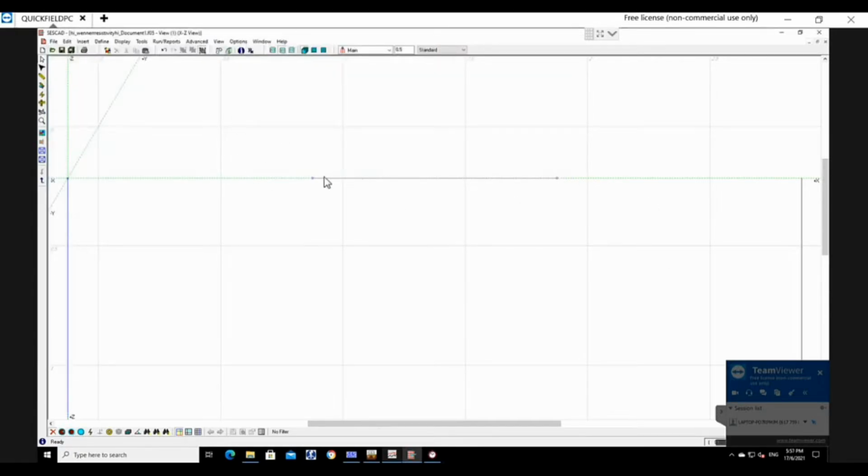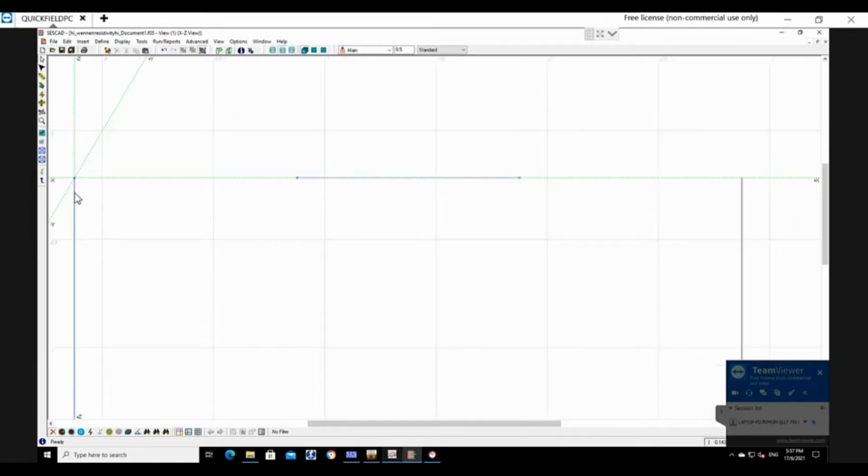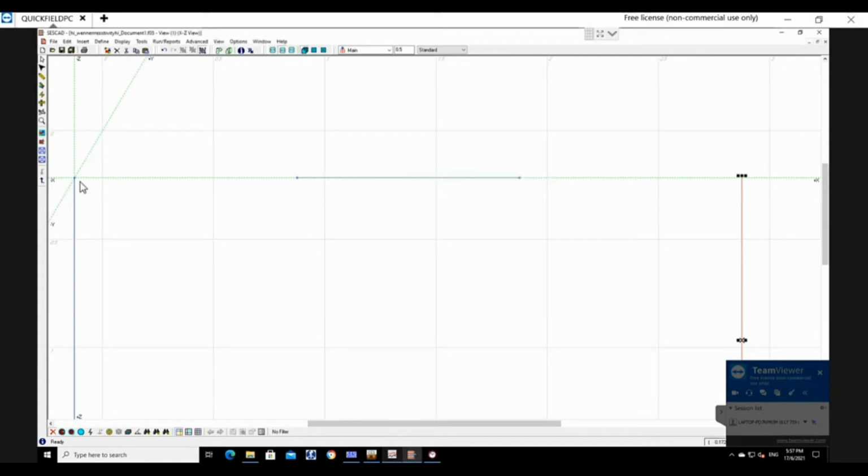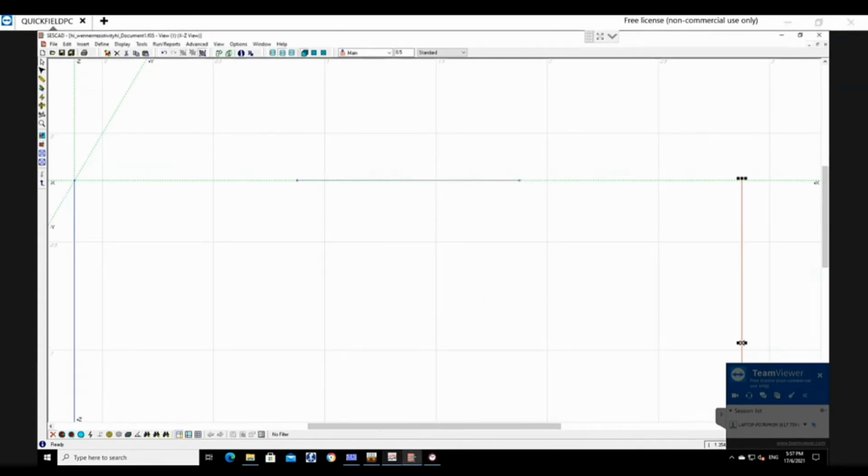For the second part, we need to change the current probe's length to 1.5 meter, and take the reading based on the data, which is from 1 to 12 with the same electrode spacing, 1 until 30 meter. So that's all for the Wenner 4-point method.